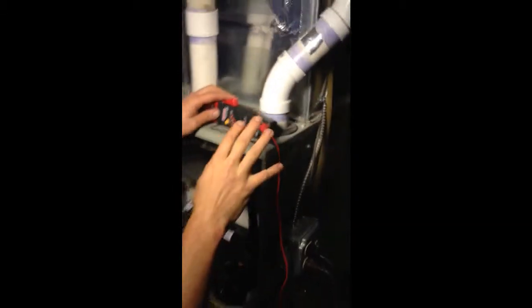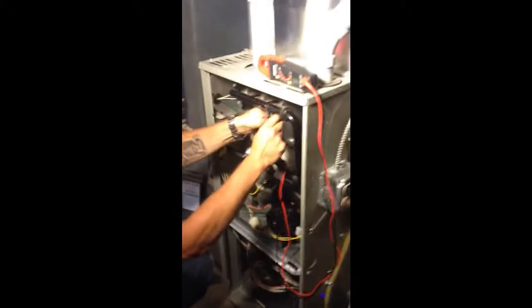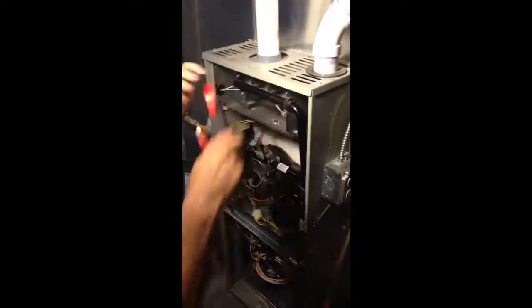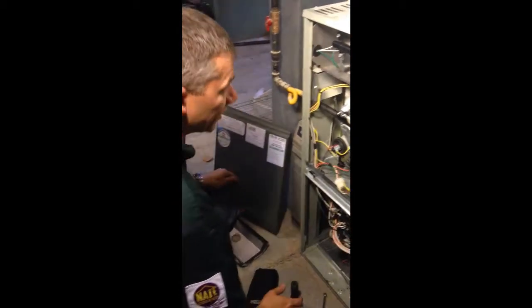And anything under 20 ohms, that's the resistance, ohms right there. Anything under 20 is good. If it was at 19, I'd recommend replacing the igniter. At 15.7, it's totally fine. Works great, showing no signs of going out. What it'll do is it'll climb up, and then over 20 it'll just hit 0 and won't work anymore. And then you're replacing that.